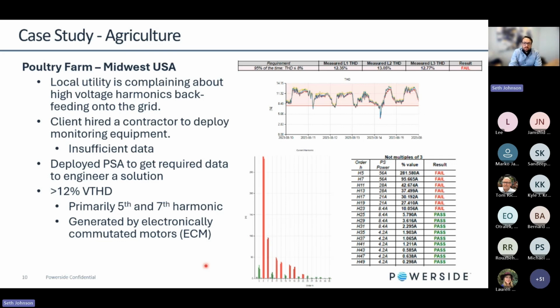So what we did is we deployed our power systems analysis program, and we pulled this profile from the customer. And you can see here from a pass-fail criteria, they were failing on all the harmonic orders up to the 23rd, and you can see that here in red. And again, this is fairly typical of a 6-pulse spectrum. Generally, the biggest offenders were the 5th and 7th, 5th being the primary. So this was a perfect application for us to provide a power quality mitigation solution.